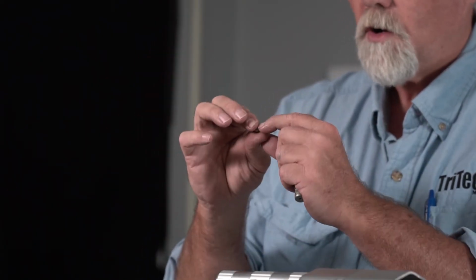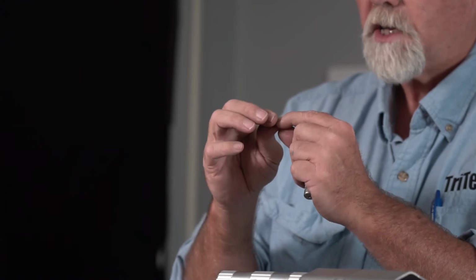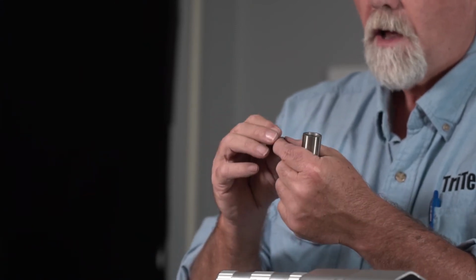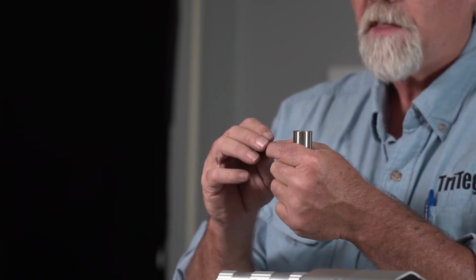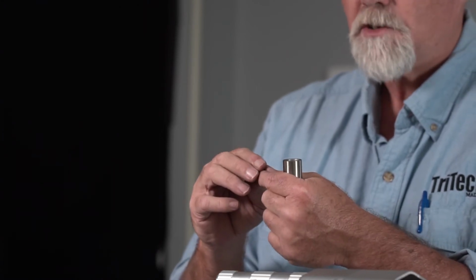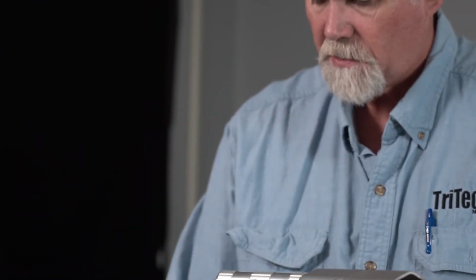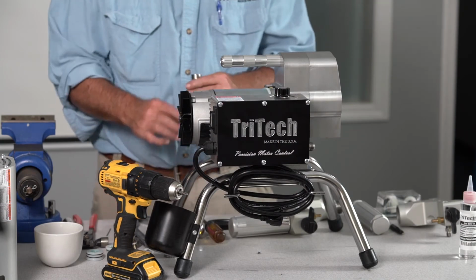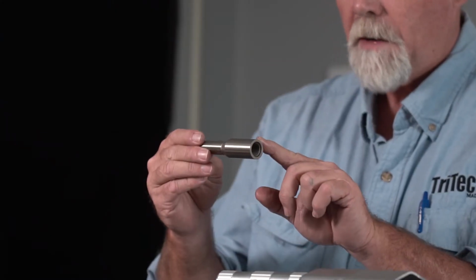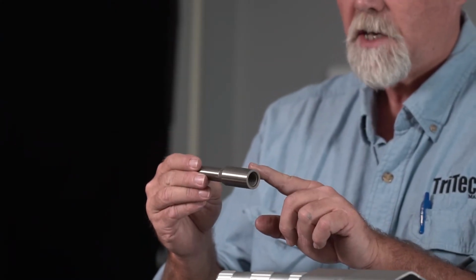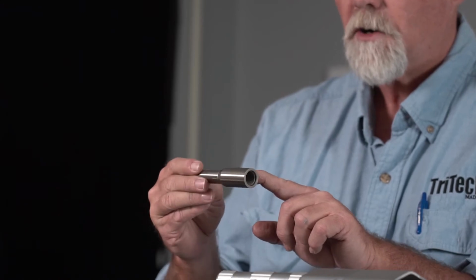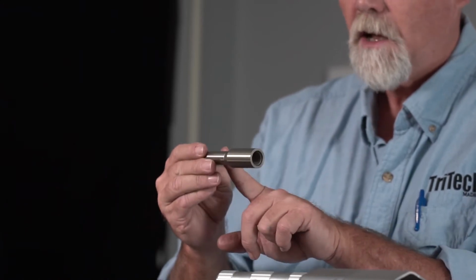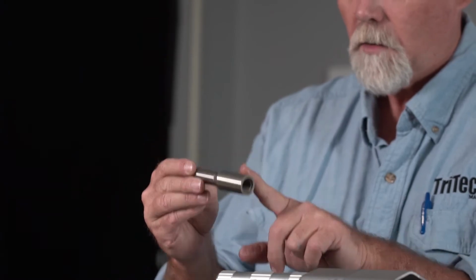Now you can examine your outlet ball. Also, we're troubleshooting, so we want to look at the condition of the ball to make sure that there's no imperfections or dents or scratches. We want to examine our piston, make sure it's in uniform condition, that there are no scratches or imperfection on the upper part of the piston and the lower part of the piston.